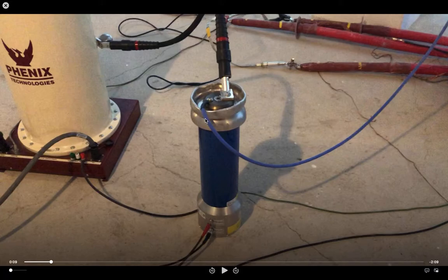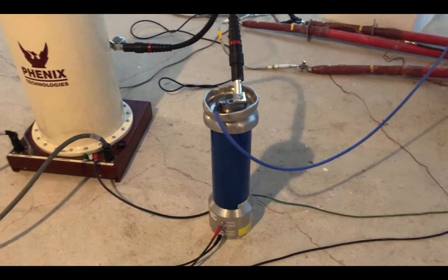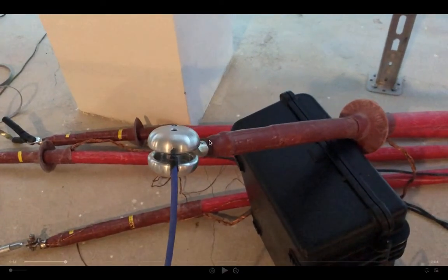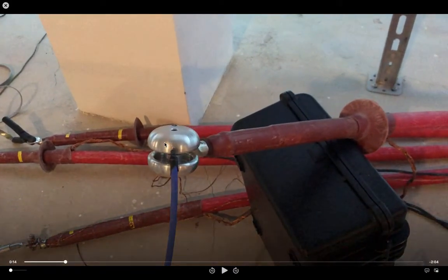From here in parallel you will see that we have a connection to the cable itself. Let me explain: this is a corona shield. A corona shield is a small metallic device which physically prevents generation of corona which might interfere with your tests. Of course, with our software we can remove that noise, but if we can help our software with some hardware interventions, then we do it.